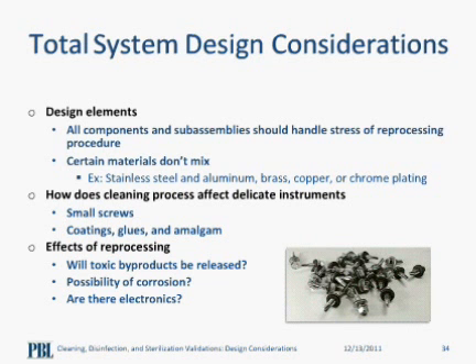What about the functionality? One of the effects of reprocessing that we have to consider is the functionality of the device after repeated reuse and exposures. Can we still get the same performance in its intended use? This is another aspect that we need to prove. The areas of concern will be the electronics, the microchips, lens, and other delicate components installed within the device. Cleaning procedures should include extra precautions for delicate parts or components like this.